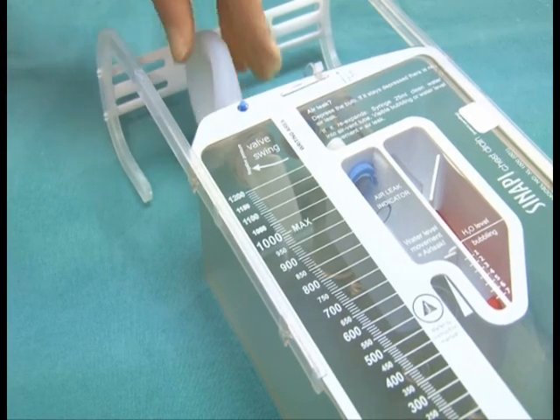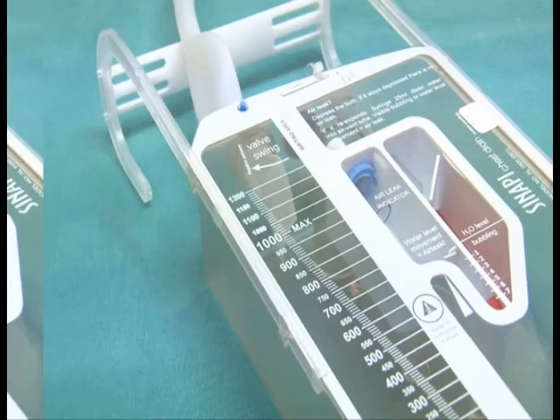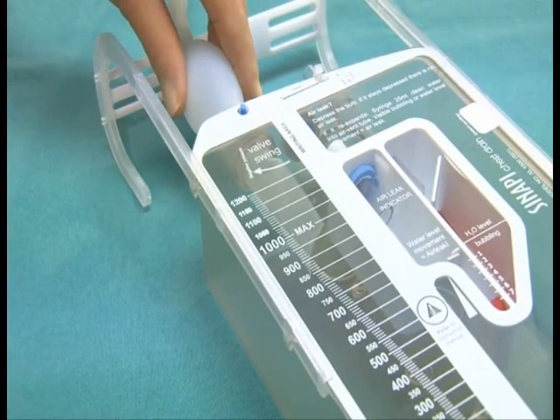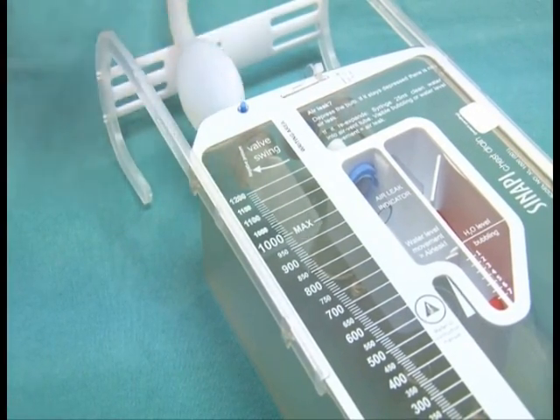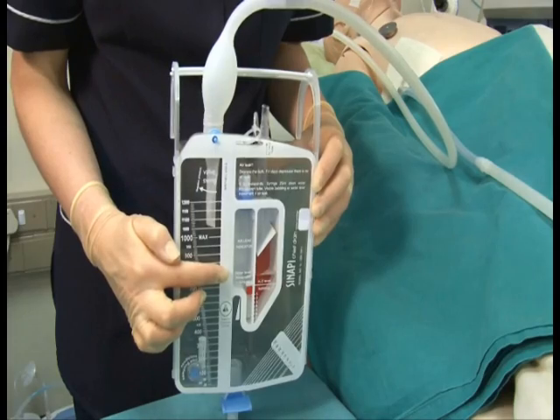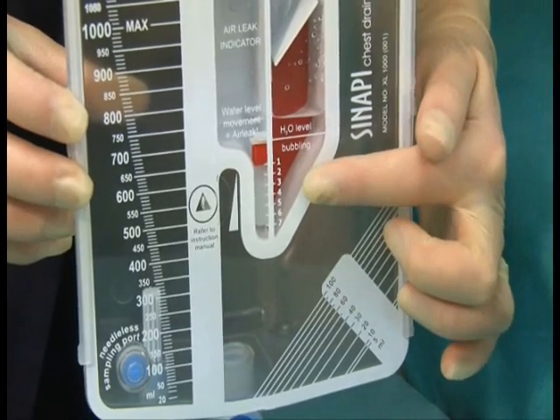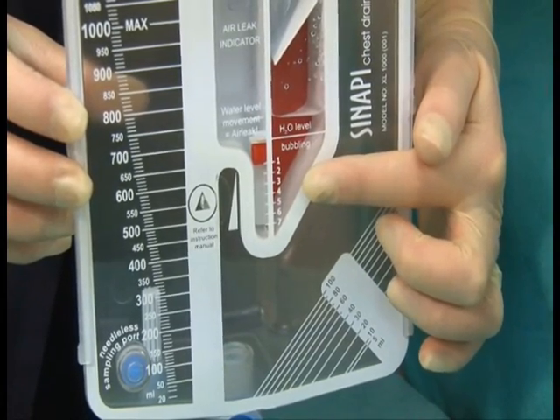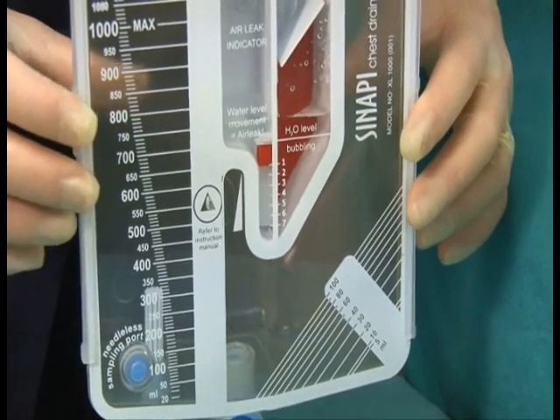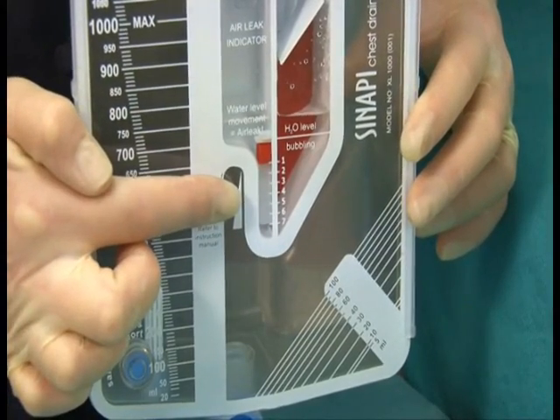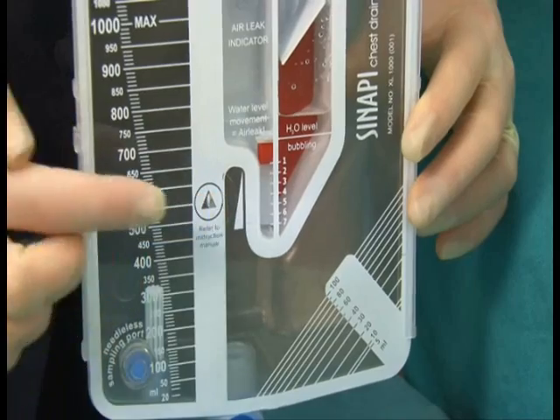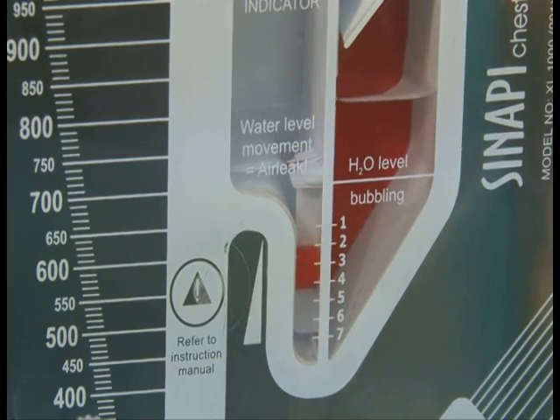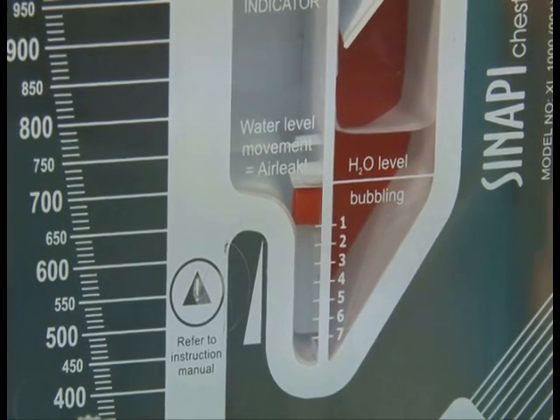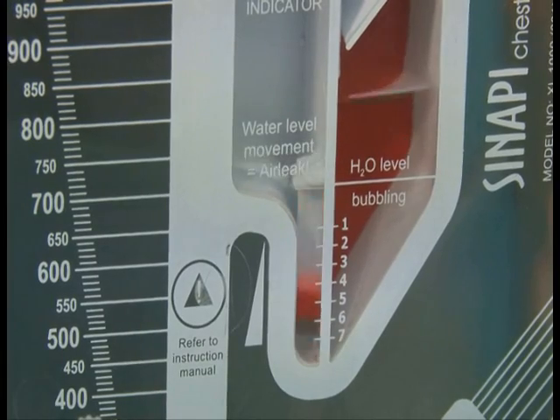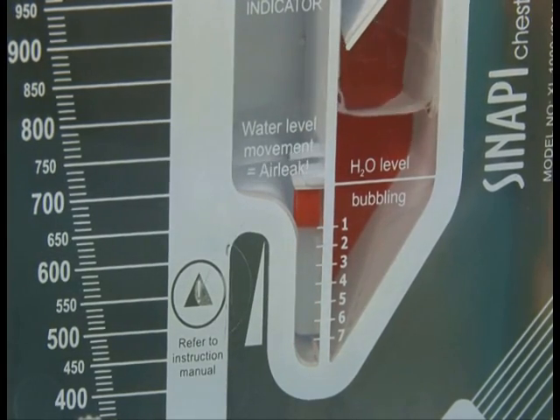Depress the bulb. If it stays depressed, there is no air leak. If it re-expands, look for bubbling in the air leak chamber. If bubbling is visible on the right side or water level movement is visible on the left side, it confirms that air is evacuating from the chest. Small water level movements indicate a small air leak and larger water level movements indicate a larger air leak.